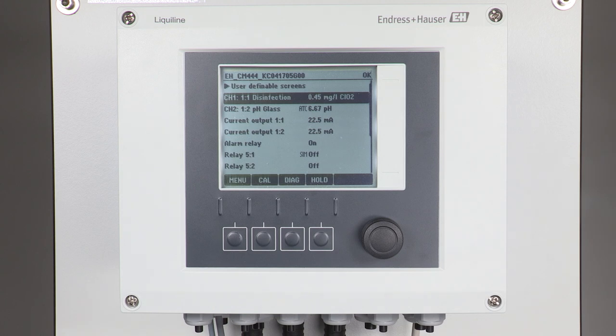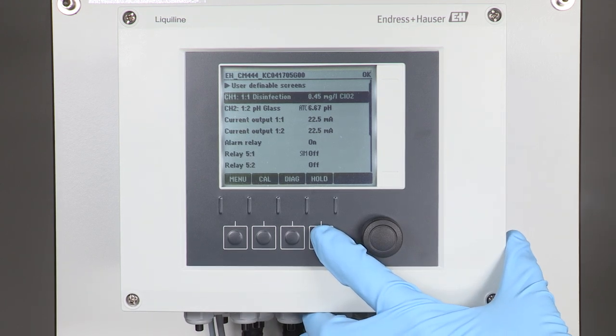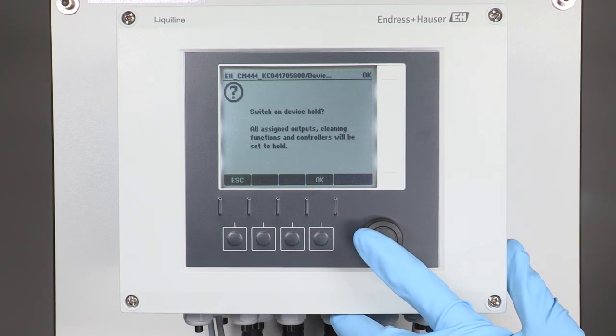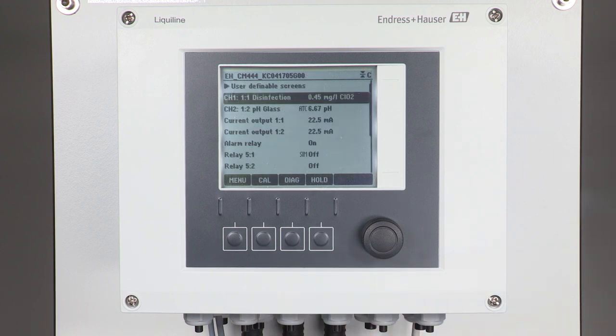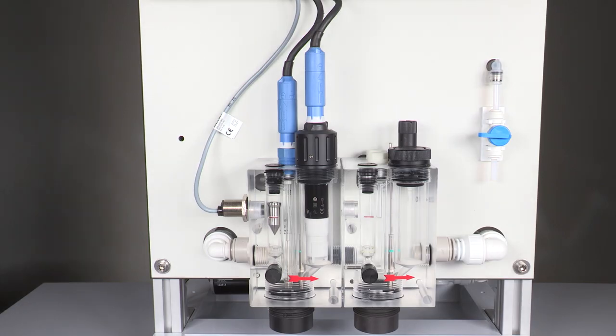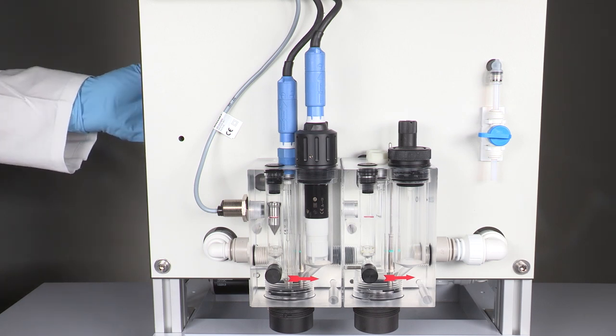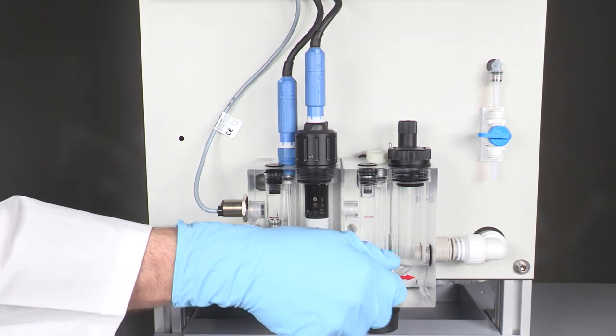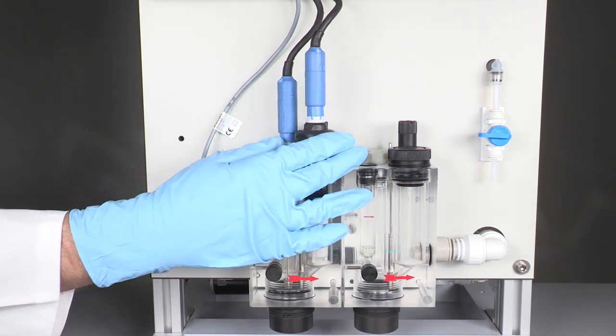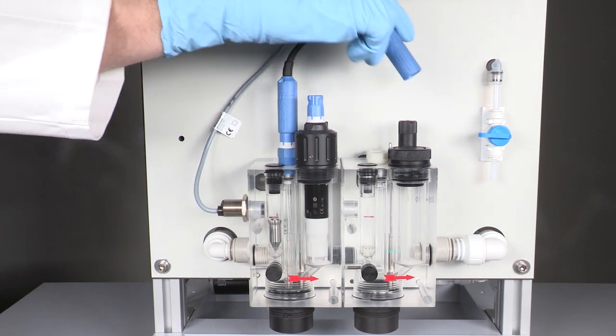Let's start with the maintenance. First we have to remove the sensor from the process. To perform this action, set the transmitter on hold and shut down the water flow. Then you can take the sensor out of the assembly.